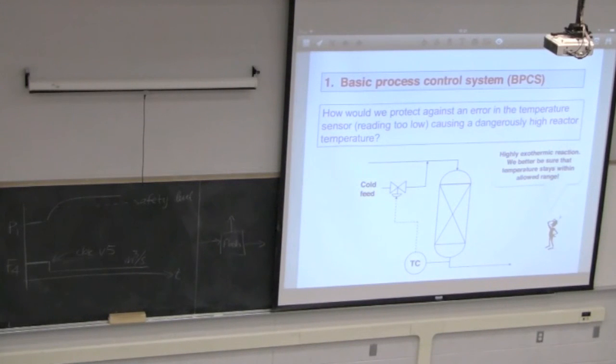So what can we do? In your controller, you can put in that if the temperature doesn't change for a specific amount of time, say 30 seconds, it's exactly the same, shut everything down, something is wrong. Okay, you can, but that's aggressive. If there's no temperature movement at all...